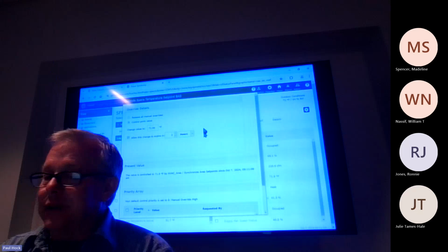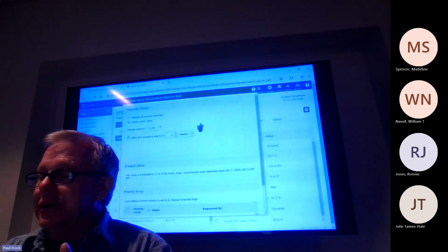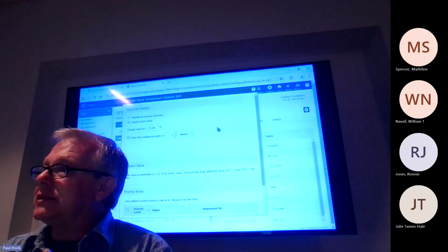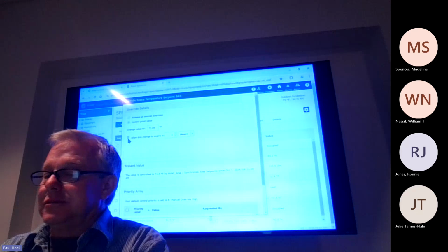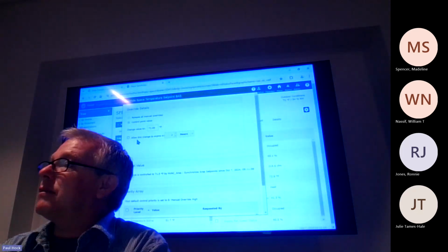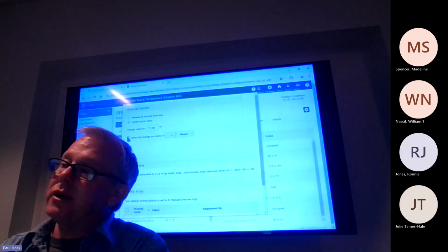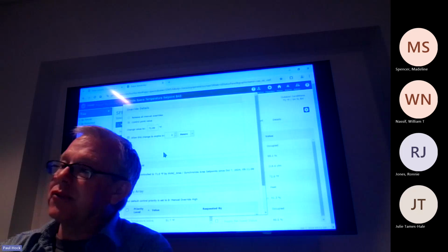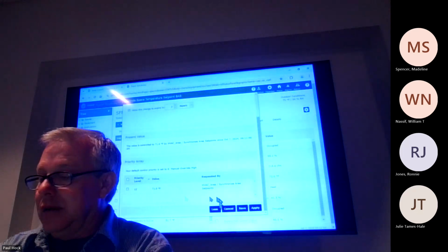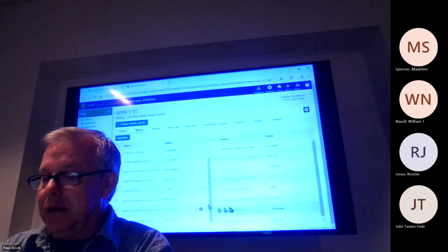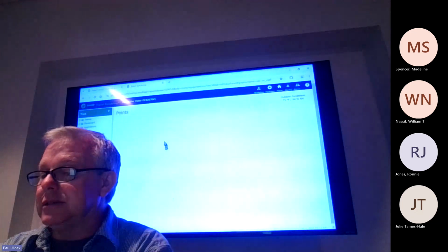And then when you click on the blue arrows, you'll see a pop up like this. See how it says this change will expire in 2 hours. If you want it to be a permanent one, you can always disable that. Otherwise, that override you put in is going to expire in 2 hours. Go back. Put this guy back in service.